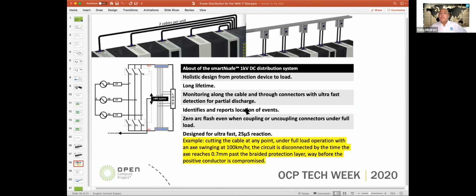And the system is designed for ultra fast reaction. The actual reaction is 25 microseconds from the time an event is detected to the time where the breaker turns off and turns the system on for the redundant portion. But just to have a visualization about this, imagine you have an axe and you swing that axe at the cable, and the cable is 1000 volts DC passing 100 amps continuously through it, and you swing the axe at it and you sever the cable. Well, the way the system is designed to work, by the time the leading edge of the axe passes 0.7 millimeter past the shield braid on the cable, the breaker turns off. So no matter how the deterioration occurs, the human safety element is paramount, and it's designed to make the system operate with safety first in place.